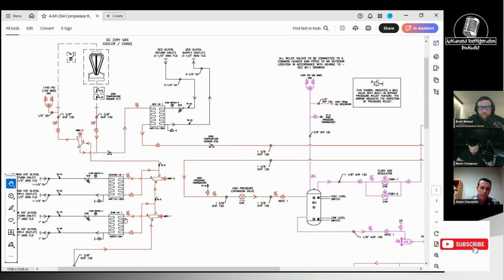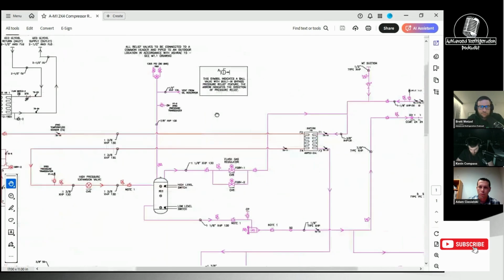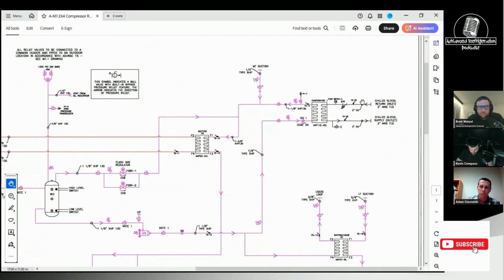We don't actually, the refrigeration is not connected to the wells at all. So the only connection, so we have a loop, which is circulating through the wells, and that warm glycol will dump back into this chilled water loop. Okay. So that's the connection. It's not shown on the schematic, but external to the rack schematic is the system schematic. Mm-hmm. And we do have a buffer tank installed on site. So think of it this way, is we've got this chilled water loop.